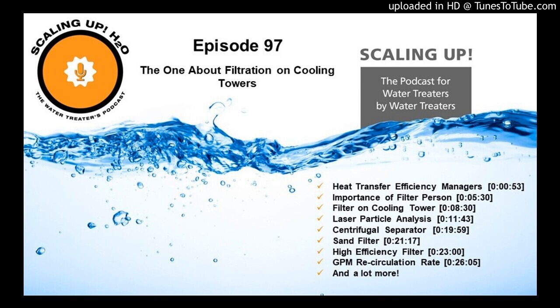One of the things about particle analyzers is the ones that are most frequently used cost maybe $8,000 or $10,000, and they are not particularly accurate. The ones that are accurate cost maybe $50,000 or $100,000. So there is a bit of a problem in the actual technology as far as the accuracy goes. But if you use the $5,000 particle analyzer, you'll get a certain reading. If you put a filter on the system, that reading will drop way down and you'll be able to show a major removal of particulates. So any particle analyzer will get you the basics.